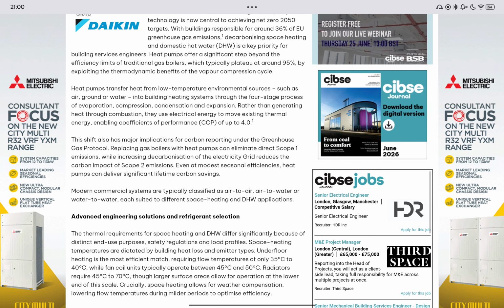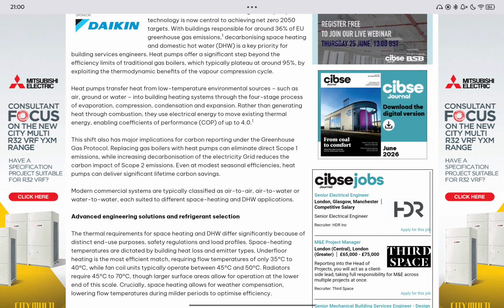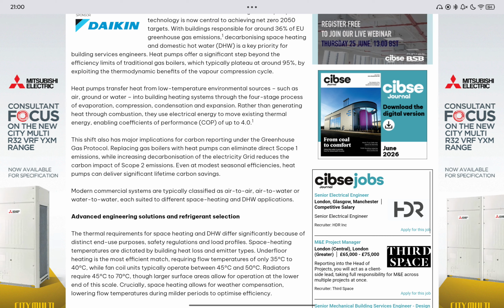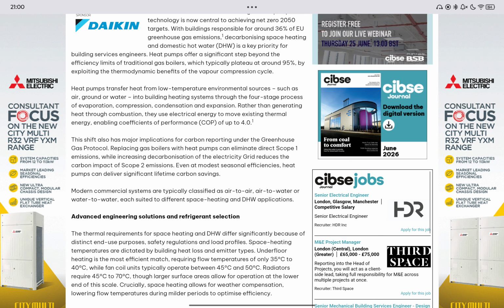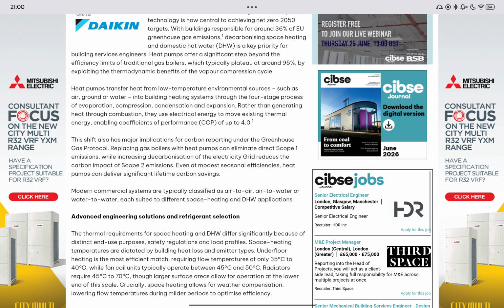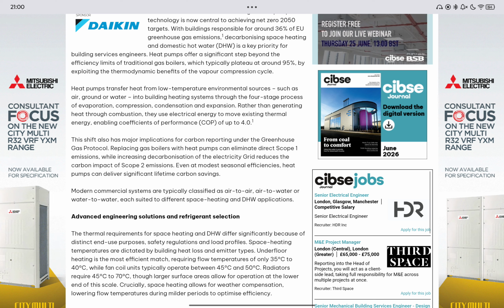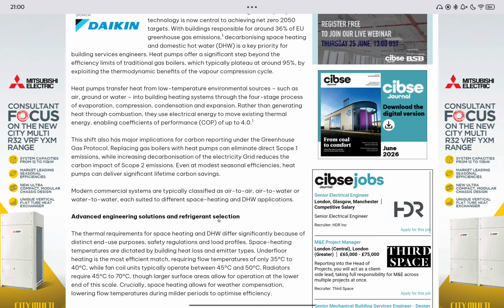Heat pumps transfer heat from low-temperature environmental sources such as air, ground or water into the building heating systems through the four-stage process of evaporation, compression, condensation and expansion. Rather than generating heat through combustion, they use electrical energy to move existing thermal energy, enabling coefficients of performance, or COPs, of up to 4.0.